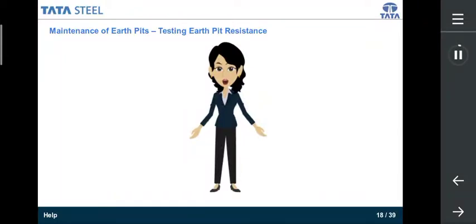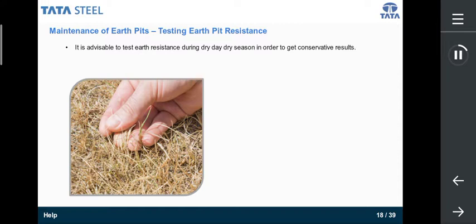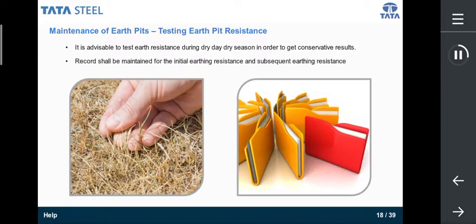Across the earth electrode and earthing lead, the voltage is found to be below 5 volts, then testing is done. The next step is to test the resistance of the earthing pit. It is advisable to test earth resistance during a dry day, dry season in order to get conservative results. Further, records shall be maintained for the initial earthing resistance and subsequent earthing resistance.